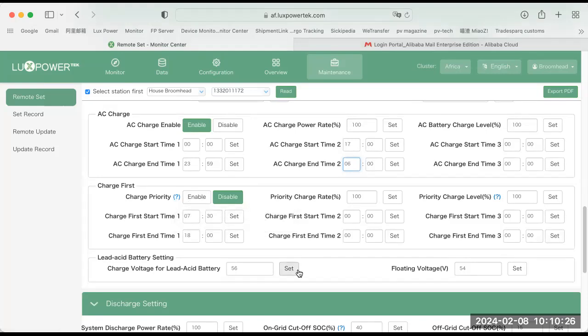But did you know that if you disable your AC charging, right? So you never ever want to charge from grid. It means that the machine will use the battery. But you can block out the times here. If you put 24 hours in here, it will never use the battery, because it sees this as a charge feature as well. When the inverter is under charge mode, it will not discharge at all, even if it's on a higher level of SOC or voltage.